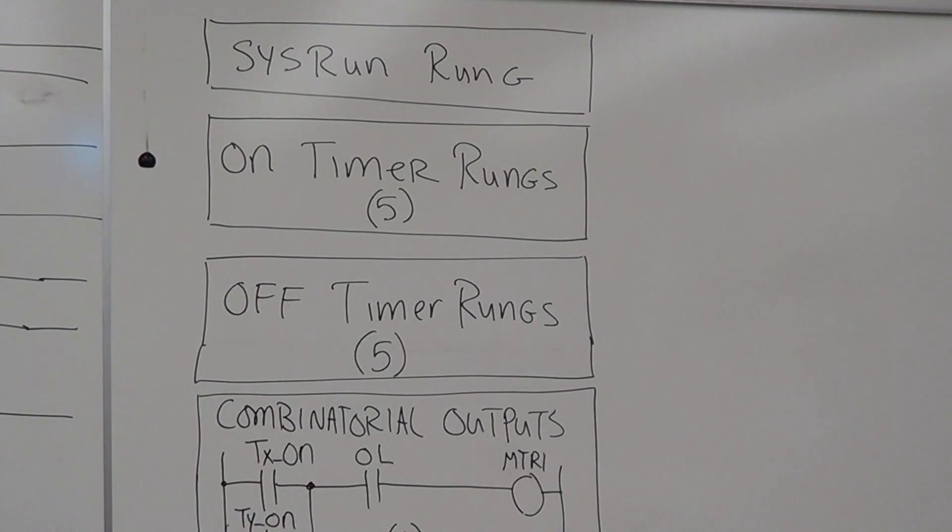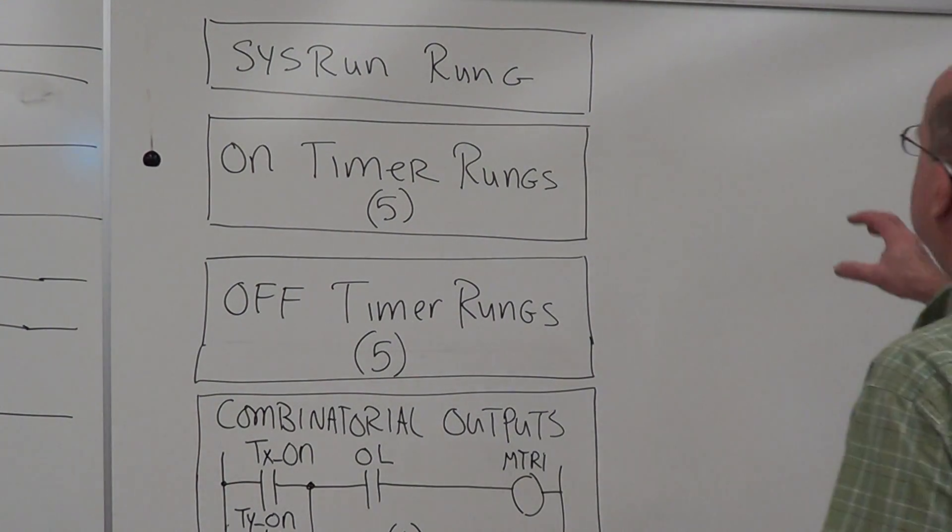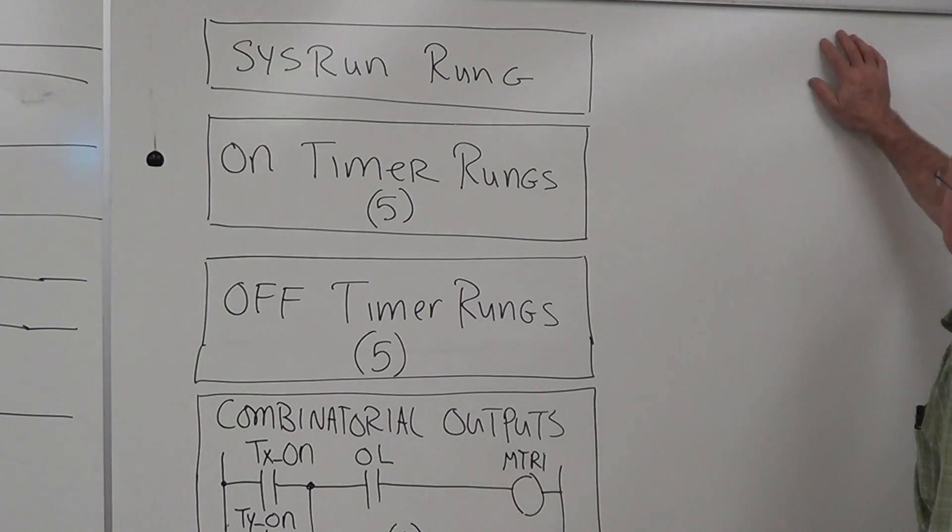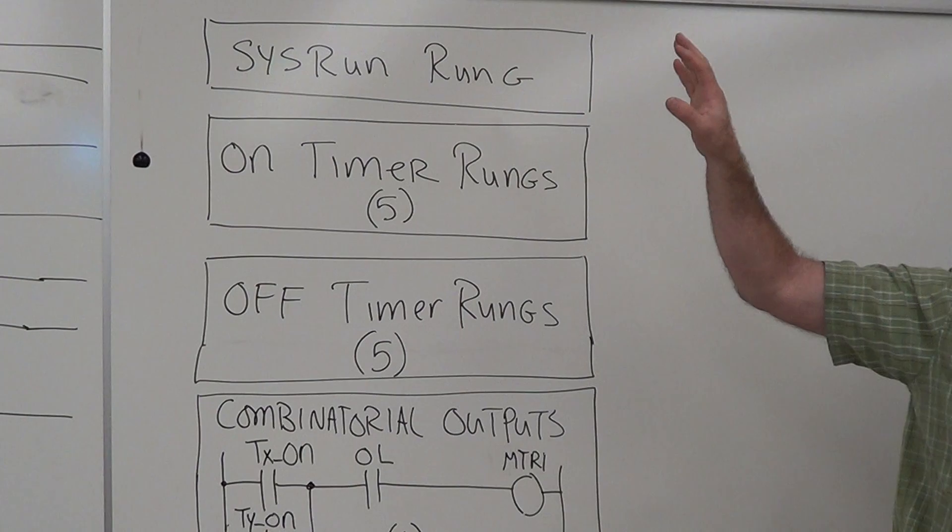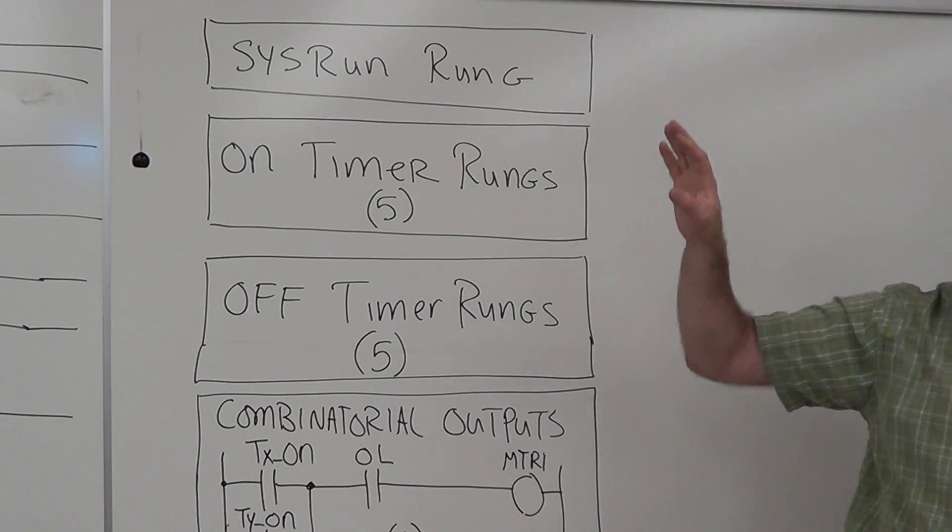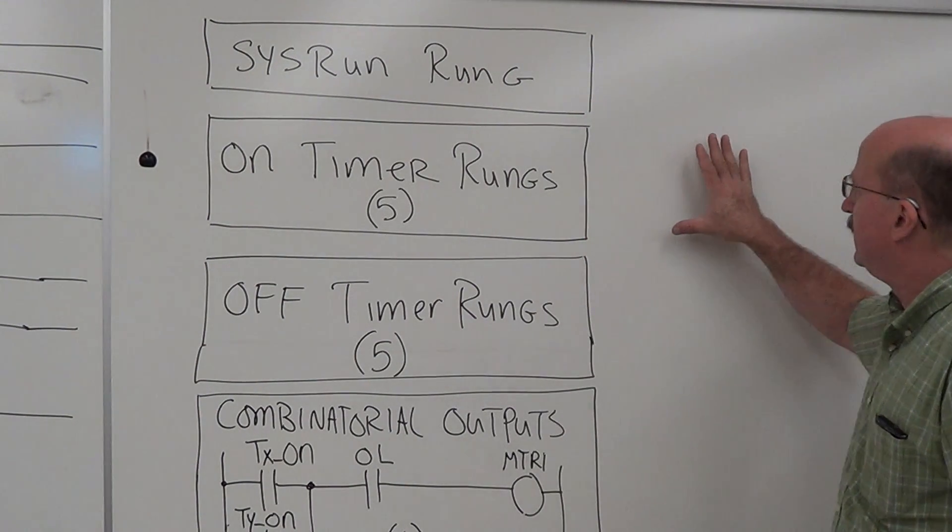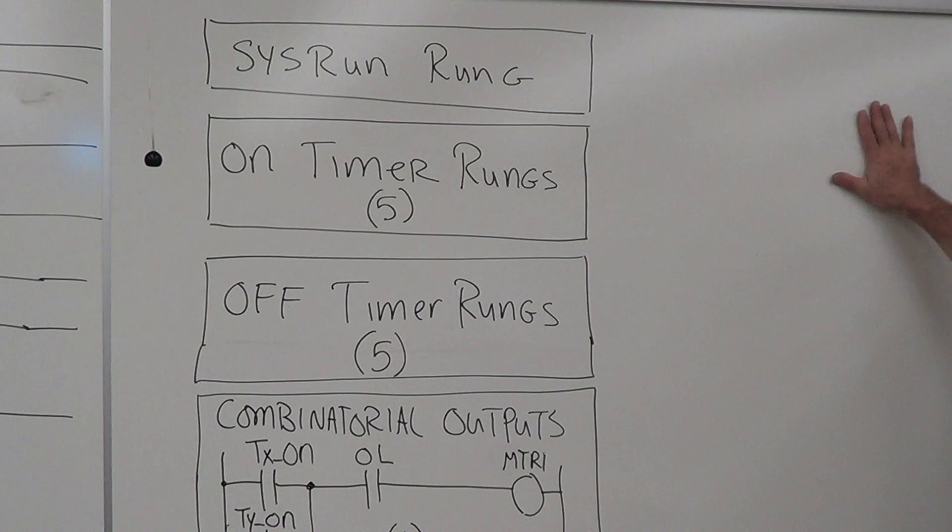Because if you start trying to throw a little bit here, a little bit there - what I see sometimes, I'll see somebody put a start stop and then put the timer in there. We already know that timers don't work in the start stop rungs, right? Then the other things I'll see are on-delay timers and off-delay timers in the same rung, and then try and stick your motor out there.